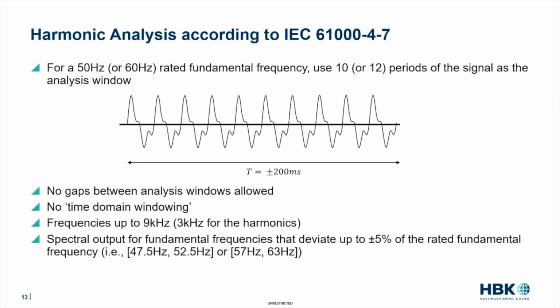Another thing is that it is not allowed to have gaps between your windows. So if you have measured, for example, from 0 to 200 milliseconds, and you have determined your harmonics for that time signal, the next set of harmonics should be determined on the next 200 milliseconds, etc. So it's not allowed to determine the harmonics over 200 milliseconds, then take a break for 200 or 350 milliseconds, and then take the next 200 milliseconds. That is not allowed. It is not allowed to have gaps between the different analysis windows. So that is what the standard prescribes.